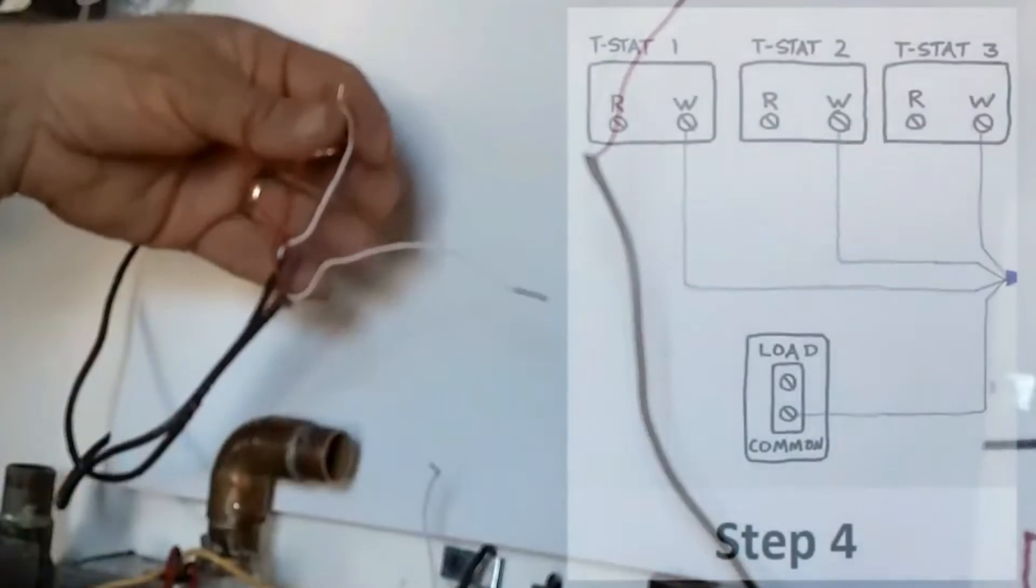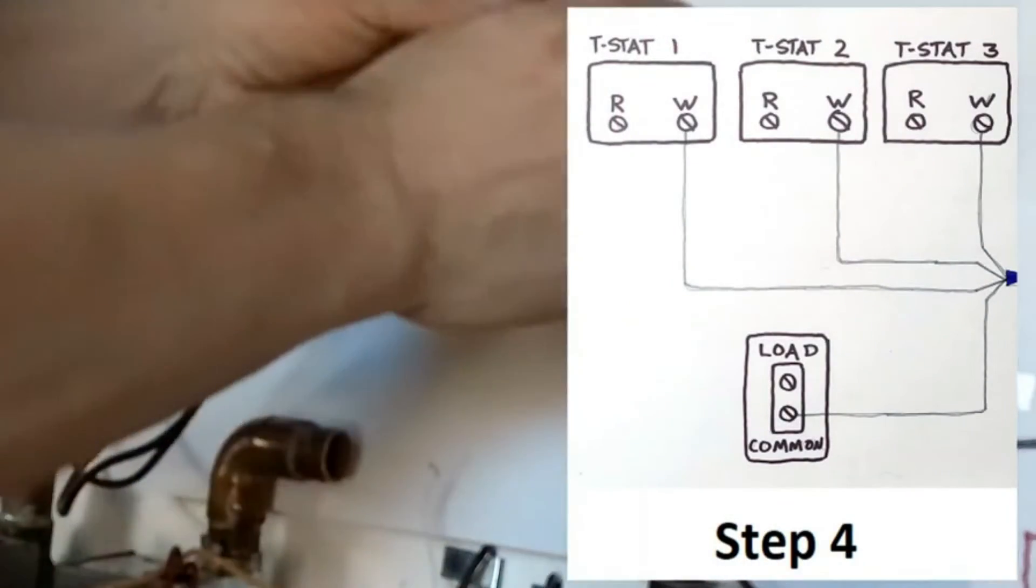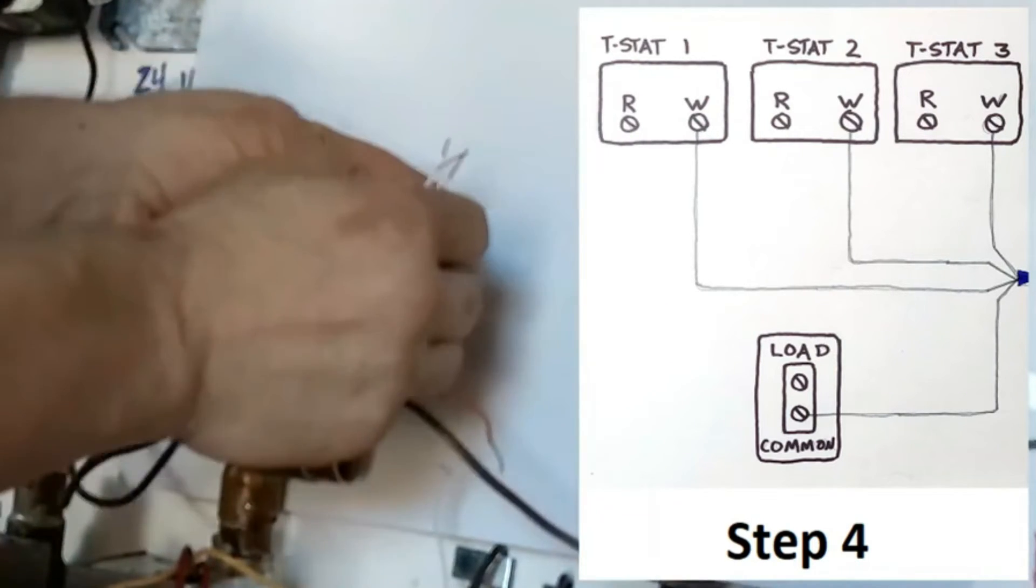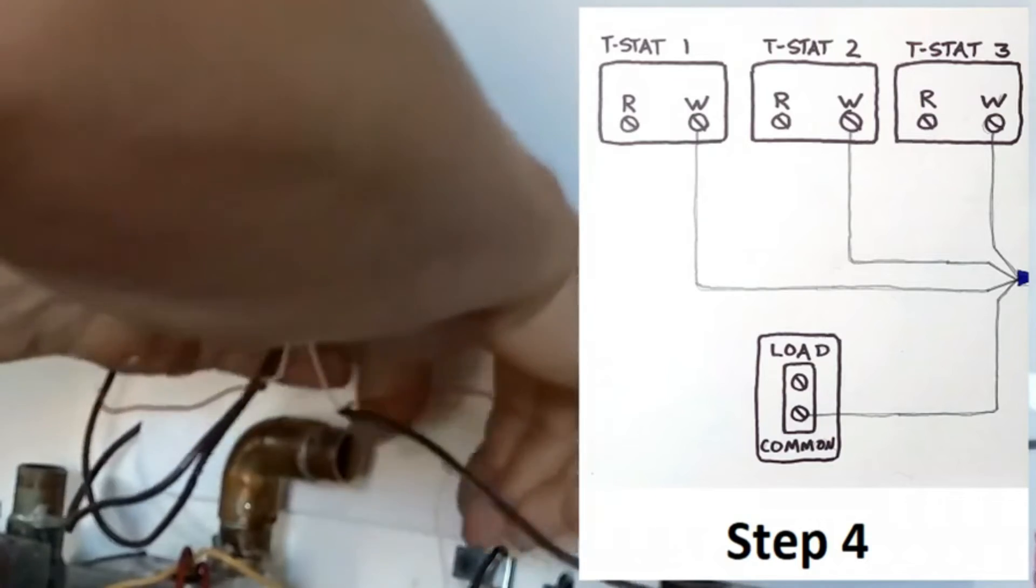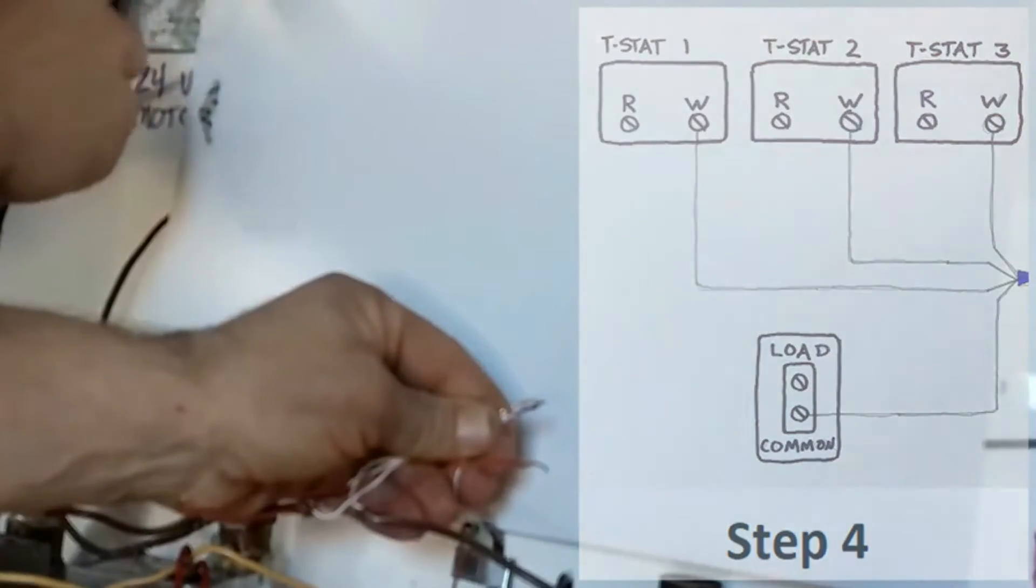Step four is to take the white wire from each one of your thermostats and bring those together. Now these are the wires that come back from the W terminal on your thermostat and these wires are going to connect to the white wire going back to your common on your external transformer.